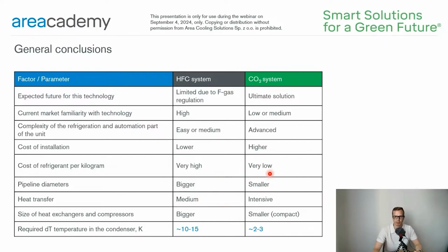than that of HFC. In HFC systems, the pipeline diameters are bigger than in CO2 installations, and the heat transfer is not as efficient as in CO2 systems. In CO2 installations, the heat exchanger and compressors are generally more compact. And finally, there is also a big gap in the required temperature difference in the heat exchangers. As an example, in a condenser for HFC, it is generally between 10 and 15, while CO2 needs a much lower temperature difference value, around 2 or 3 kelvins.